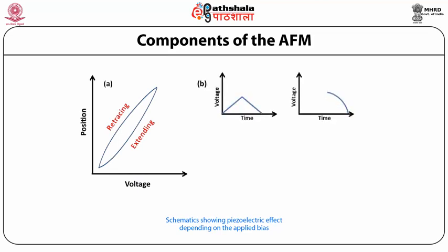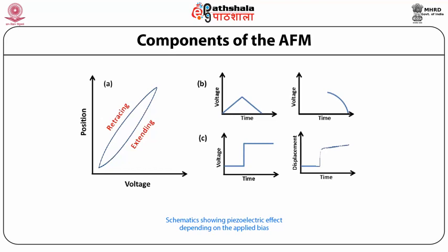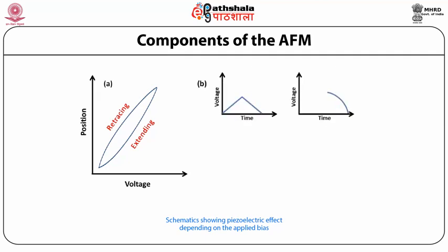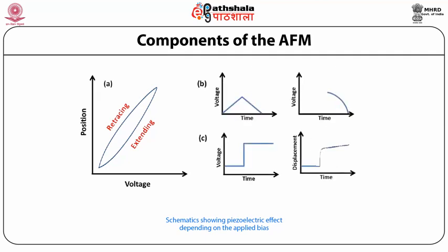The same process is repeated when the piezo is retracted from its position. This produces forward and reverse scan directions that show hysteresis behavior between the two scan directions. Nonlinearity and hysteresis can cause feature distortion in SPM images and have to be properly corrected.